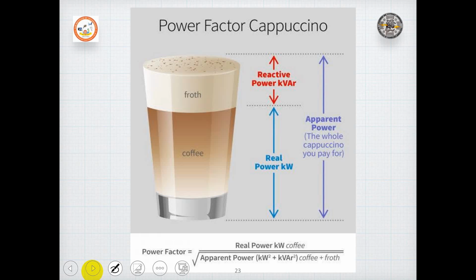Whenever there is a lower power factor, the quality of the power can go down. There are varieties of reasons that a site may have poor power factor, but the main cause normally is inductive loads such as transformers, AC motors, welding equipment, arc furnaces, and fluorescent lighting. Using such kinds of loads can reduce the power factor. So the higher the power factor, the better the quality of the power.